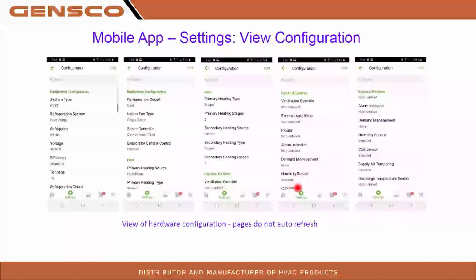Of course, if you have humidity sensor, if you enable CO2 sensor and you have nothing landed on that CO2 sensor spot, it'll prompt you with an alert, right? If it's not installed, it won't look for it. So keep that in mind. Discharge temperature sensor, you're going to have that with the economizer. So if you have an economizer selected, and this shows not installed in your app, you will get an alert.